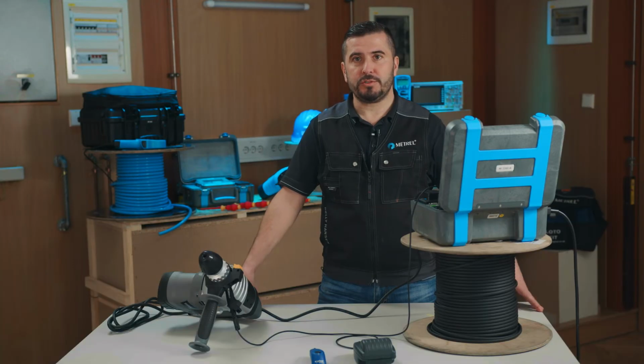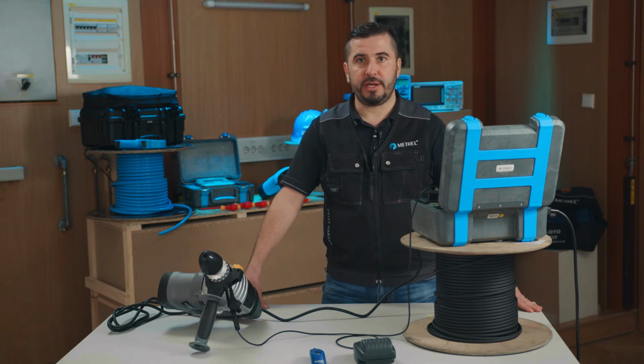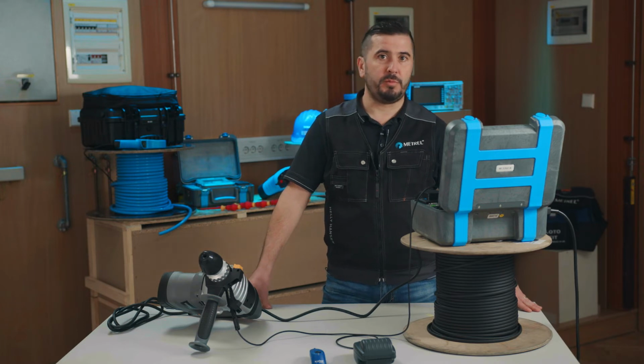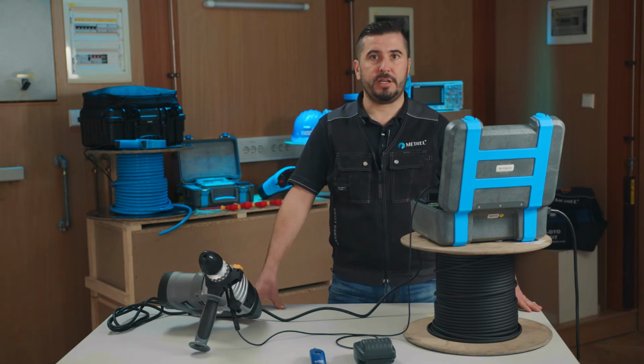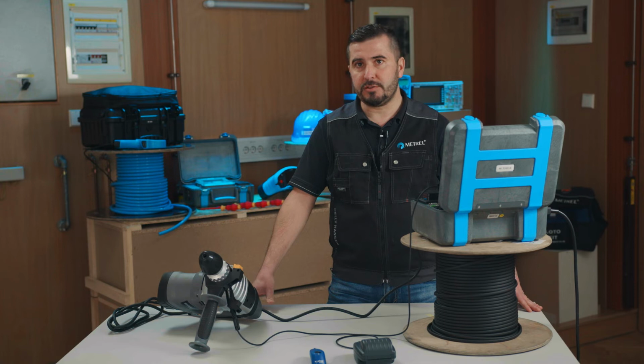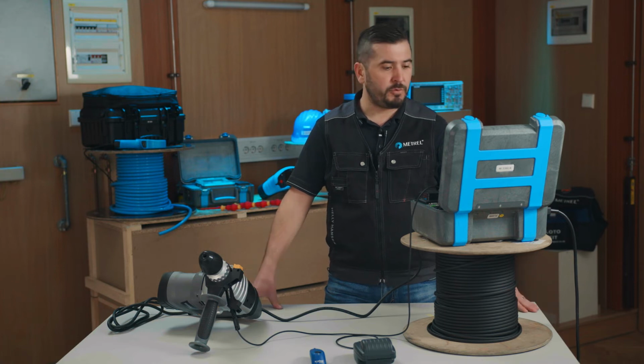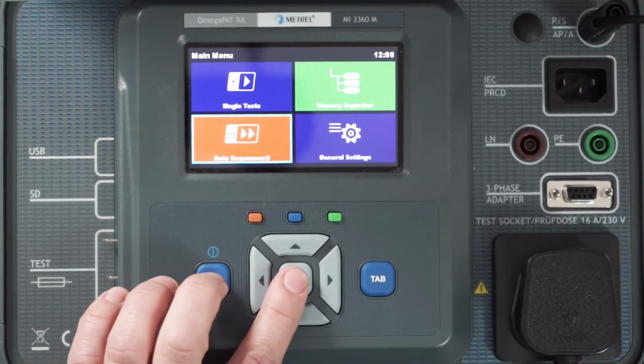We now enter the auto sequence menu and choose the correct test sequence. We will select it from the group General, which is designed based on information provided in the 5th edition Code of Practice for In-Service Inspection and Testing of Electrical Equipment. Inside the menu, we search for the group Portable Handheld, from where we select a test sequence dedicated to class 2 appliances, and of course for performing live testing.